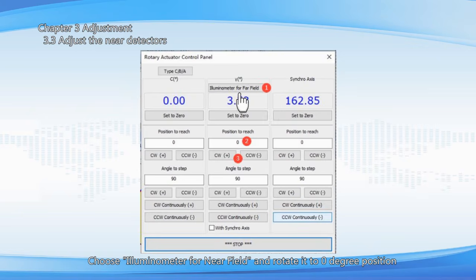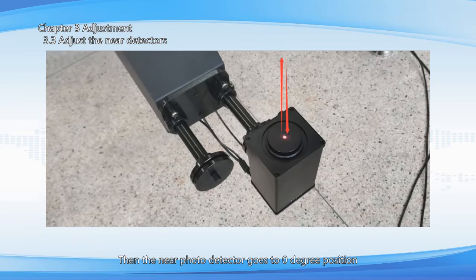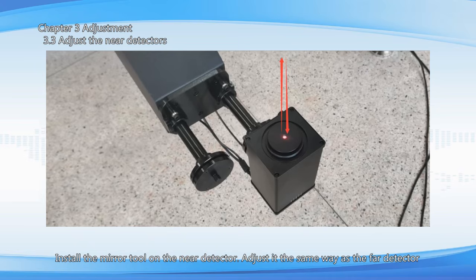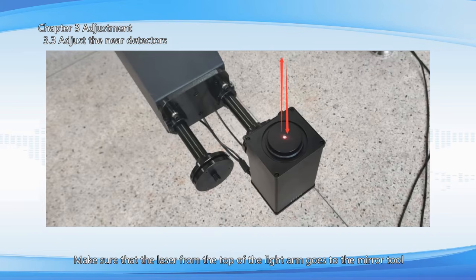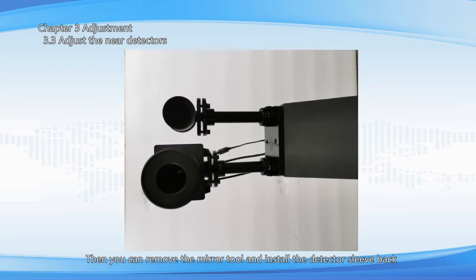Adjust the near detectors. Choose illuminometer for near field and rotate it to 0° position. Then the near photo detector goes to 0° position. Install the mirror tool on the near detector. Adjust it the same way as the FAR detector. Make sure that the laser from the top of the light arm goes to the mirror tool and the reflected laser goes back to its original position. All the screws need to be tightened after the adjustment. Then you can remove the mirror tool and install the detector sleeve back.